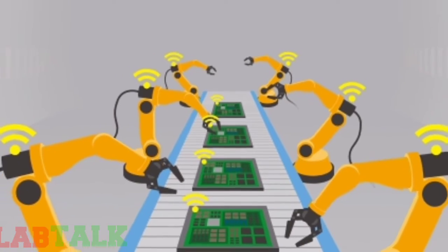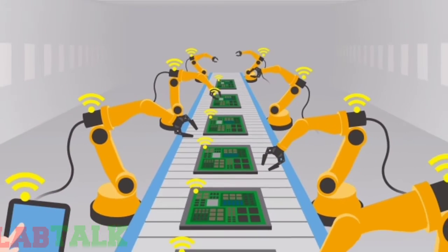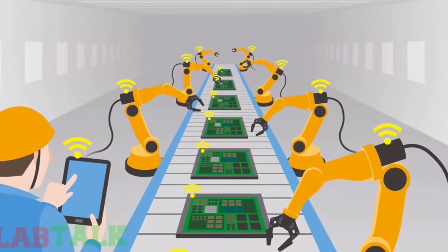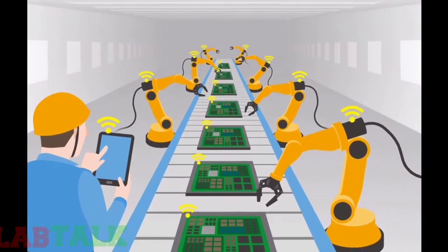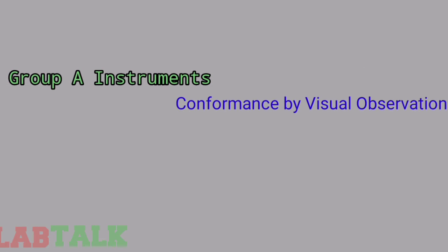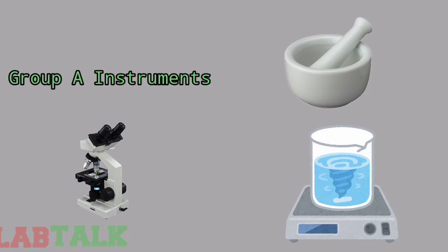Modern laboratories typically include a suite of tools. These vary from simple spatulas to complex automated instruments. The instrumentation in the clinical laboratories has improved a lot and state-of-the-art automations are being placed all over in most of the clinical laboratories. Equipment in laboratories can be grouped under 3 categories. Group A instruments. Conformance of Group A instruments to user requirements is determined by mere visual observation and no independent qualification process is required. This type of equipment in Group A includes light microscopes, magnetic stirrers, mortar and pestles, ovens, spatulas, vortex mixers.